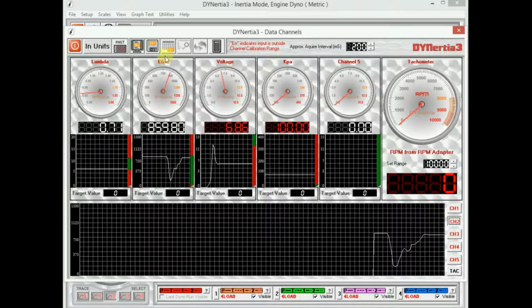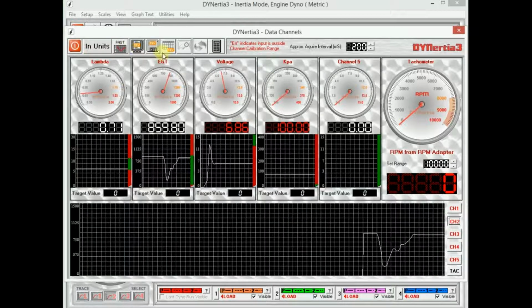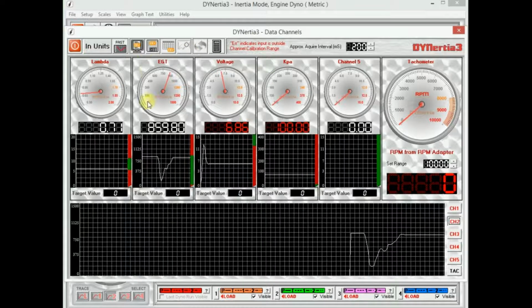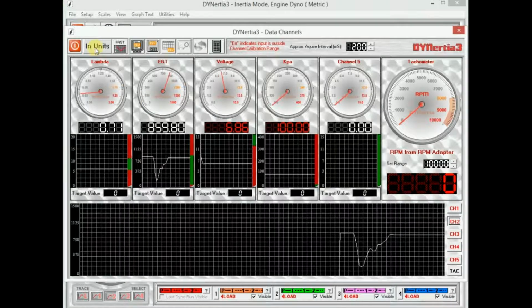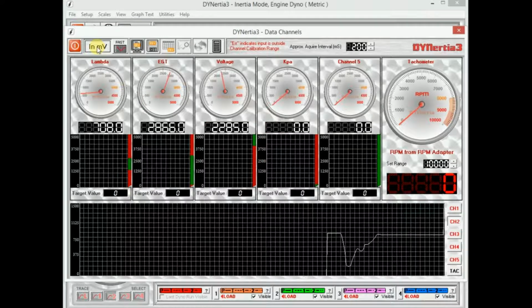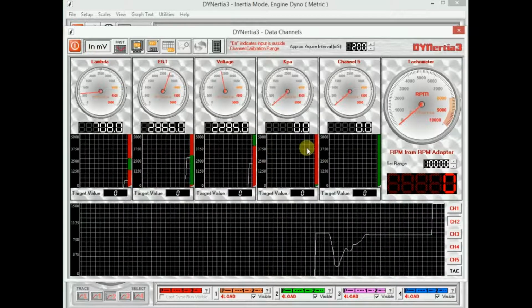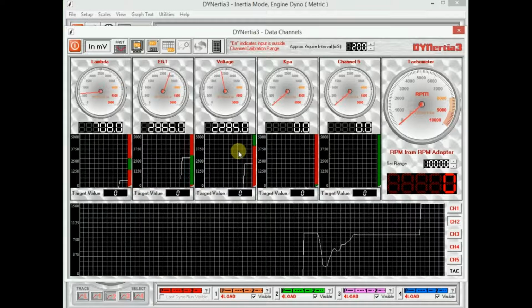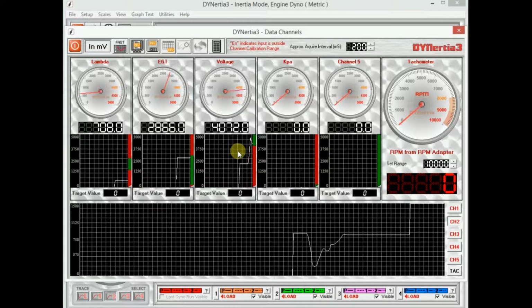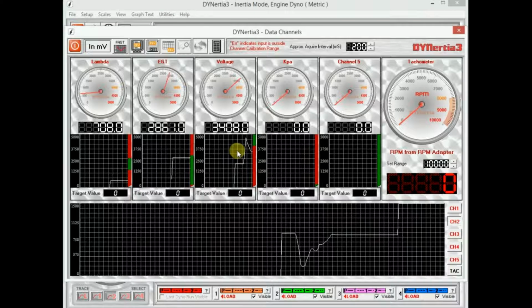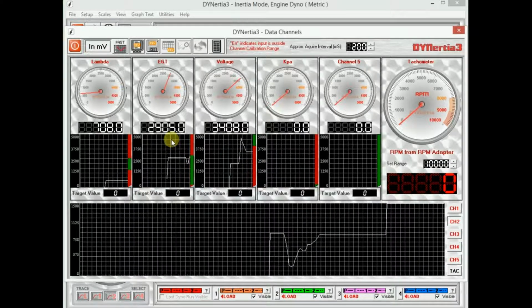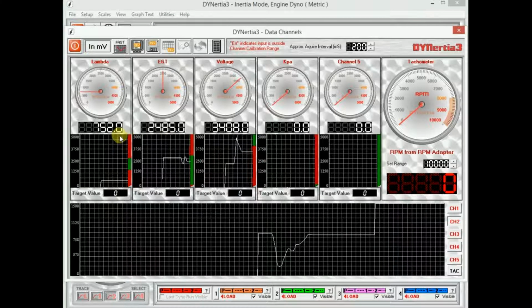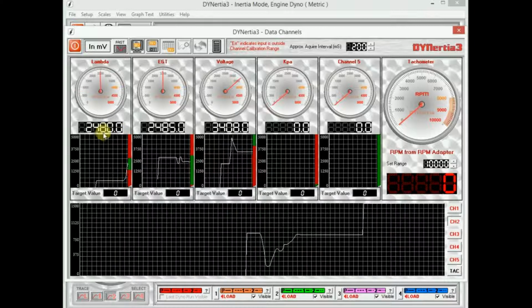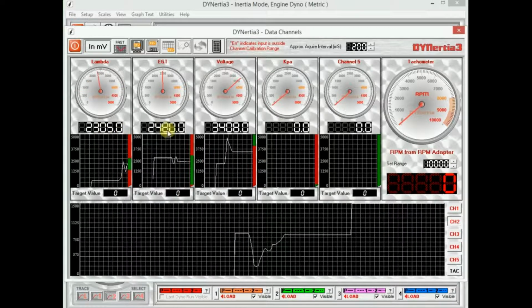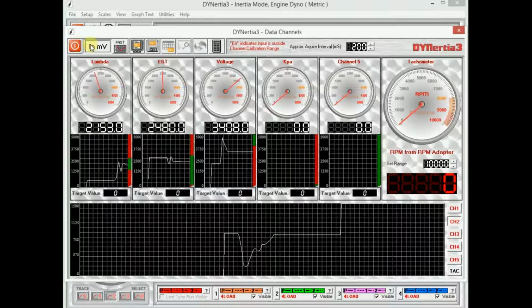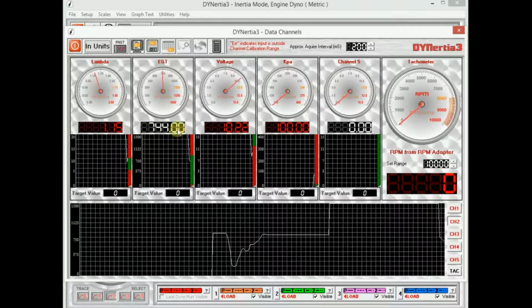I can also log it from within here, save it to a file, and display it in millivolts. So this is the actual voltage coming into the hardware. Very handy for troubleshooting - if a reading doesn't make sense, you come and check that you actually have a sensible voltage coming into the system. When I go back to units, I get my converted and scaled value.